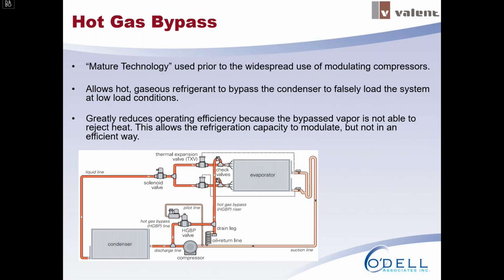As you'll see in that schematic, the hot gas after it leaves the compressor, a part of it is routed back to the evaporator. So essentially, with that bypass, you're introducing a false load onto the evaporator, and you're artificially reducing the efficiency of that evaporator to modulate its capacity. So it works to modulate, but it's really not efficient at all. And the modulation that we're seeing now is almost exclusively done by modulating compressors, and in fact, that's all that Valent offers. And we just find it to be a much better solution.